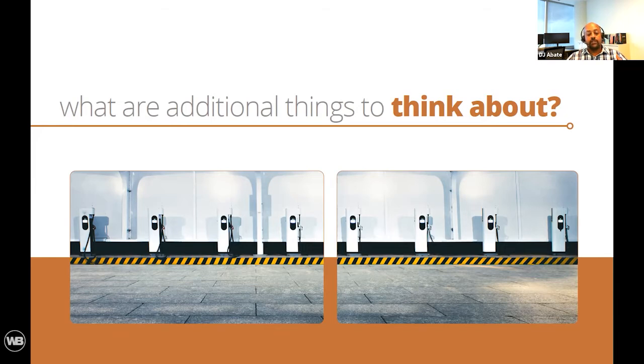A detailed investigation of the electrical system would need to be conducted to determine the available spare capacity. Depending on the quantity of chargers to be installed and the available spare capacity in the existing electrical service, it may be required to provide a new electrical service, and we see that happening a lot on most projects.